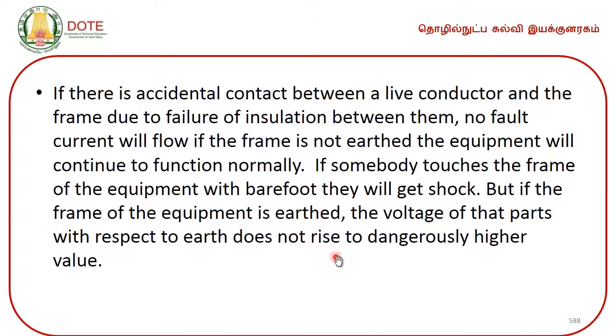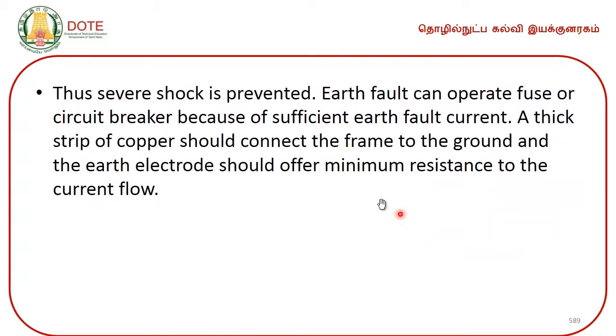not rise to dangerously higher value. Thus, severe shock is prevented. Earth fault can operate fuse or circuit breaker because of sufficient earth fault current. A thick strip of copper should connect the frame to the ground, and the earth electrode should offer minimum resistance to the current flow.